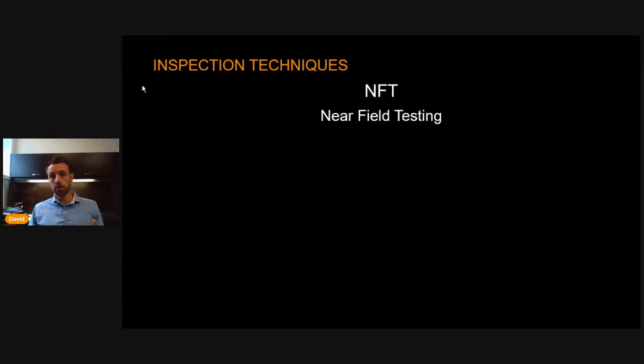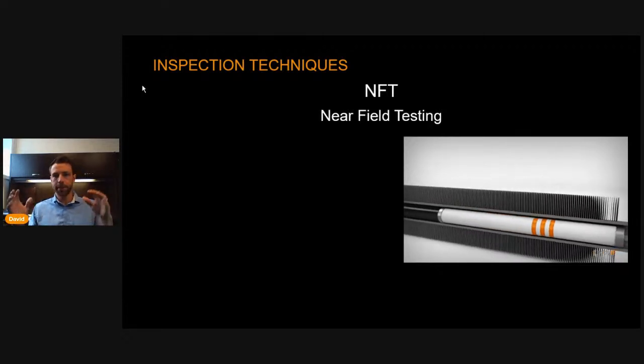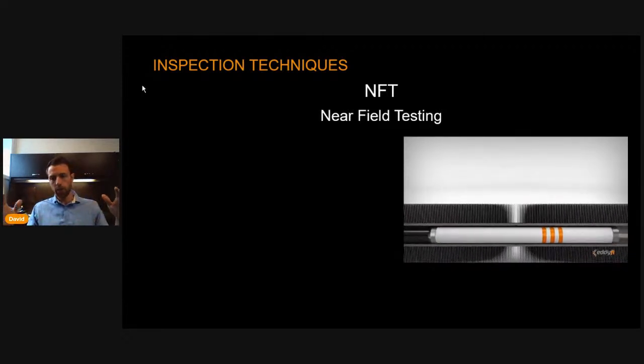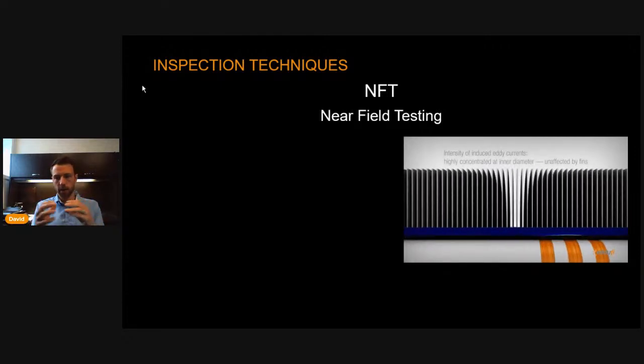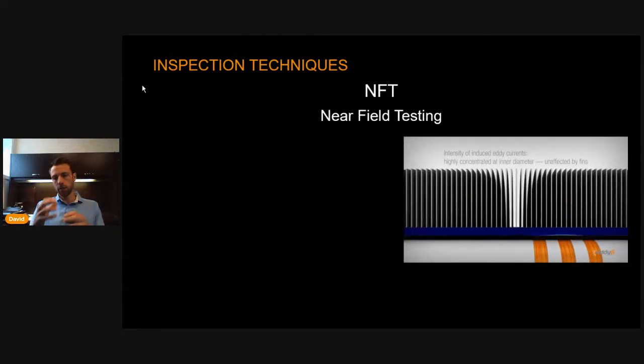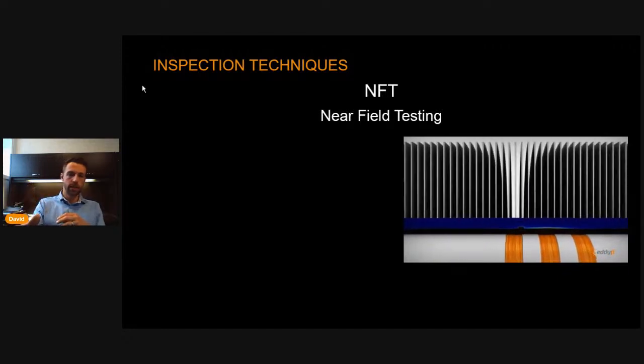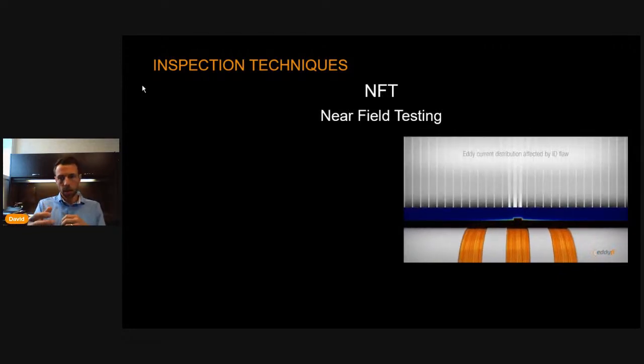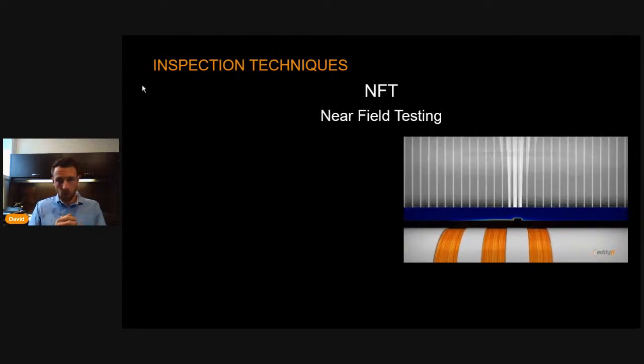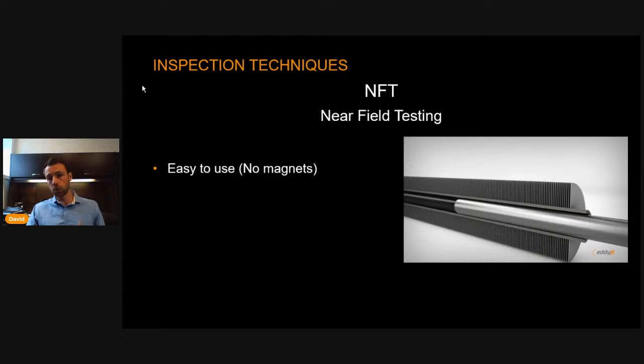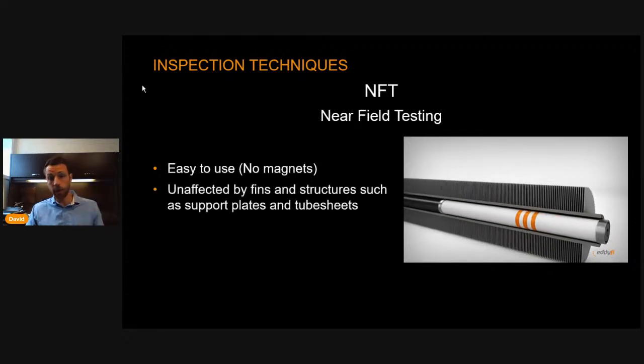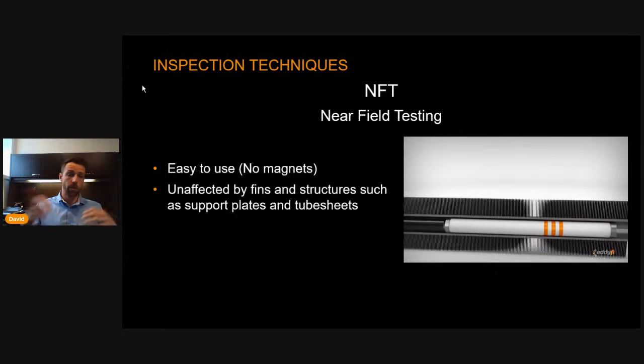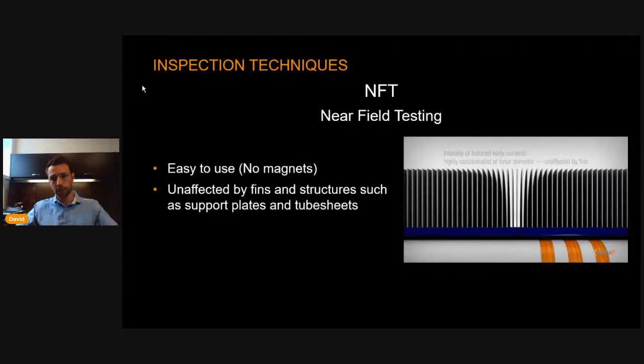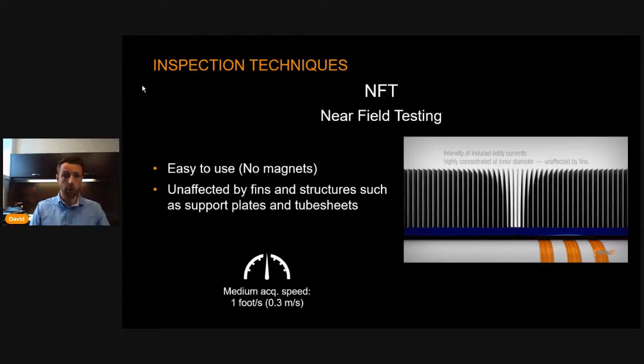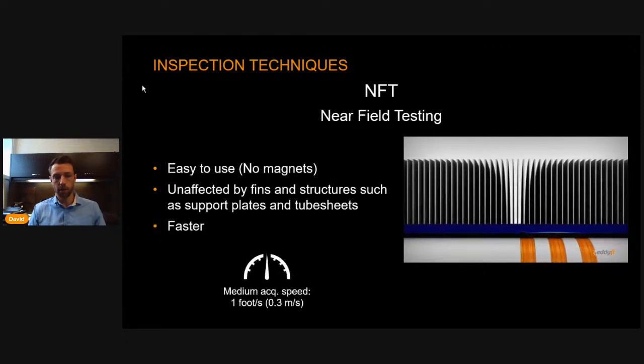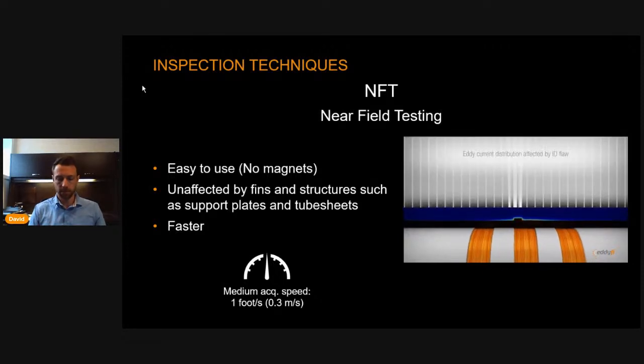The next one is going to be near field testing. Near field is a little bit the same principle as remote field. However, we bring the receiver and the drivers closer together, so we only measure or see the inside signal, the inside response of the tube with this probe. It's easy to use, and it doesn't require any magnets. It's unaffected by the structure. We only see the inside of the tube. So whether you have a support plate, fins, or tube sheet, it doesn't impact the near field results. And it's faster than IRIS. We're talking about 1 foot a second, about 0.3 meter per second.